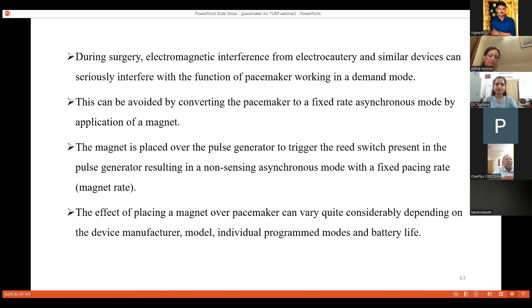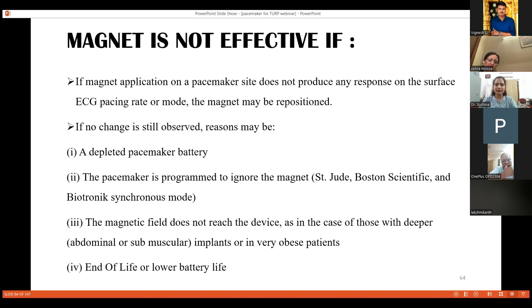The effect of placing a magnet over the pacemaker can vary quite considerably depending on the device manufacturer, model, individual program modes, and the battery life. In a few cases, the magnet may not be effective. If magnet application on the pacemaker site does not produce any response, we have to reposition the magnet. If there is still no change, the reasons can be a depleted pacemaker battery, or the pacemaker is insensitive to the magnet, like in devices from companies such as St. Jude, Boston Scientific, or Biotronik in synchronous mode. In these modes, it will be insensitive to the magnet. The magnetic field may also not reach the device if it is deeply seated, like in abdominal or submuscular placement or in obese patients. Also, if there is end of life or low battery, then also the magnet will not be effective.